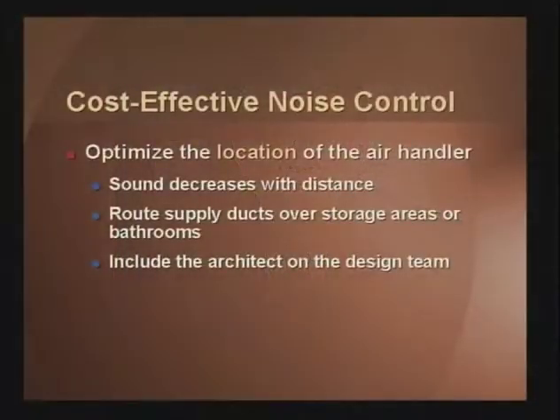First, take a look at the location of the air handler. Remember that sound, of course, decreases with distance. Don't place the rooftop over a highly sensitive space. If it's indoor equipment, route the supply ducts over storage areas or bathrooms. These spaces are generally less sound critical. The noise level will go up in the bathroom, but generally that's not a problem. In fact, you can say it's a productivity enhancement because being louder, people might get out faster. Include the architect on the design team.